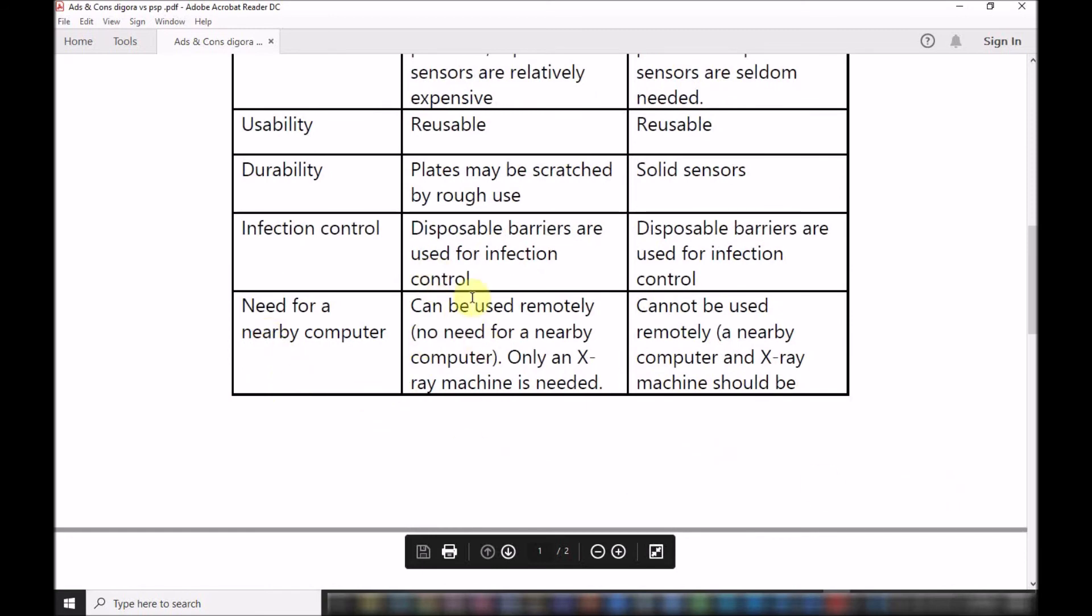The need for a nearby computer: the indirect type can be used remotely so you don't need a computer just next to your clinic because you're going to capture the image and then you take it to a scanner, and then the image will show on a computer which is attached to the scanner. But with the direct type, you cannot. You have to have a computer because these are USB type cables that are directly attached either to a desktop computer or to a laptop computer. Either way, you need a computer just exactly next to the x-ray machine or your clinic so that you will have the image displayed readily on the computer.